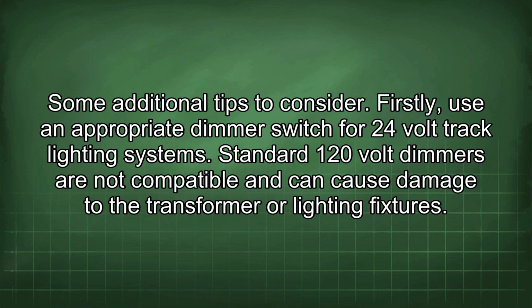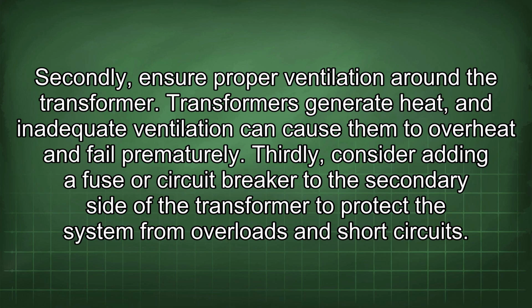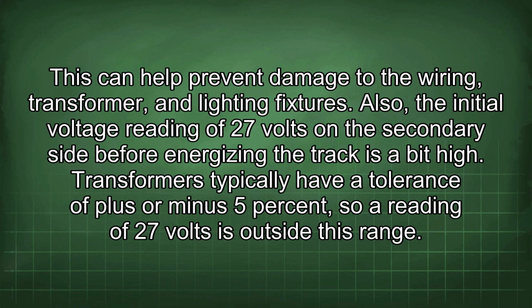Some additional tips to consider. Firstly, use an appropriate dimmer switch for 24-volt track lighting systems. Standard 120-volt dimmers are not compatible and can cause damage to the transformer or lighting fixtures. Secondly, ensure proper ventilation around the transformer. Transformers generate heat, and inadequate ventilation can cause them to overheat and fail prematurely. Thirdly, consider adding a fuse or circuit breaker to the secondary side of the transformer to protect the system from overloads and short circuits. This can help prevent damage to the wiring, transformer, and lighting fixtures.